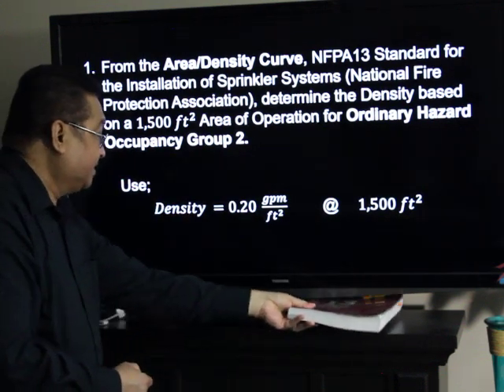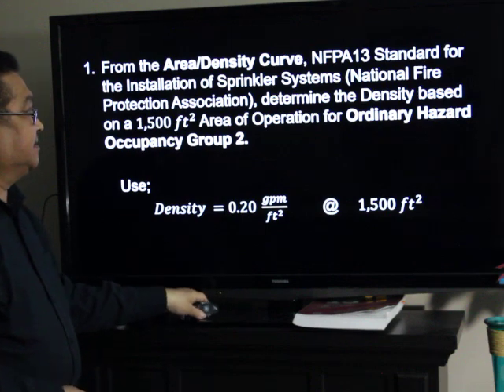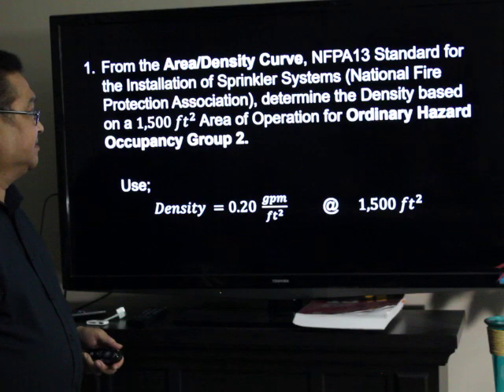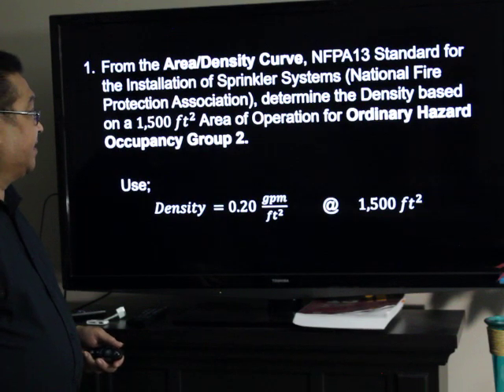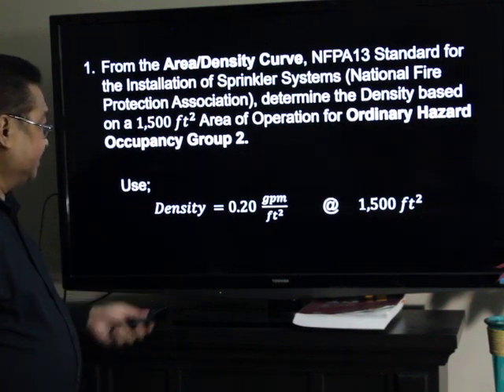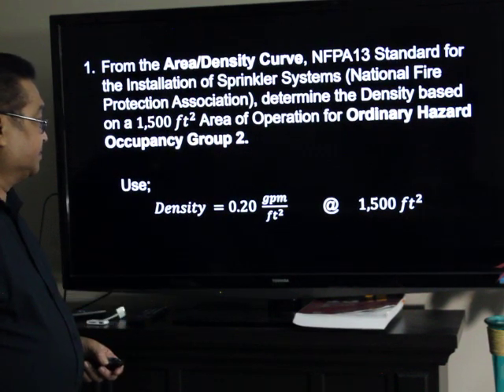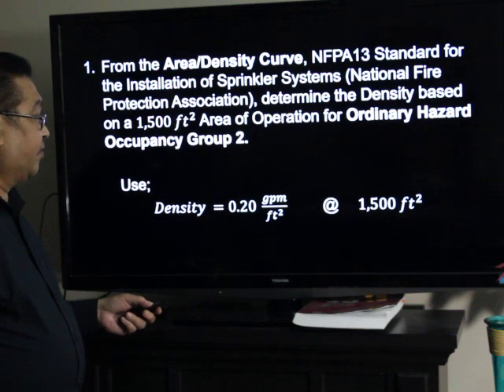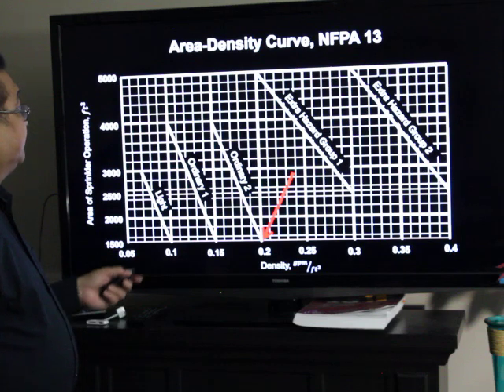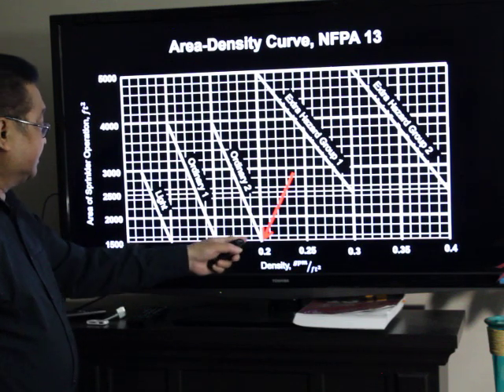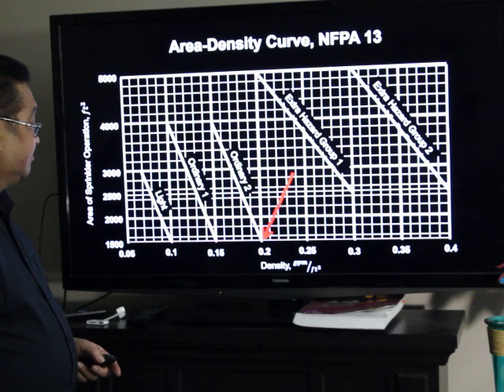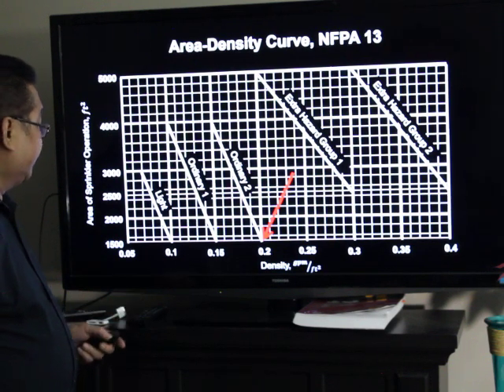We determined the density based on an area of 1,500 square feet of Ordinary Hazard Occupancy Group 2. So, density: 0.2 GPM per square feet at 1,500 square feet of area operation. From the area density curve, you can see this point in here, which is shown, pointed by the red arrow.